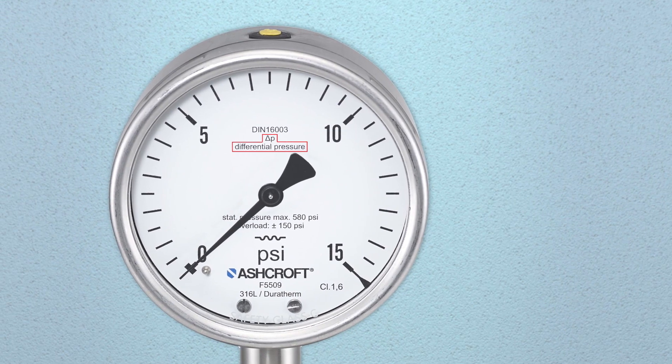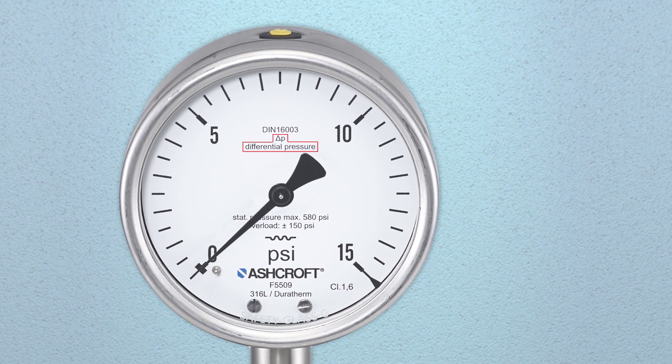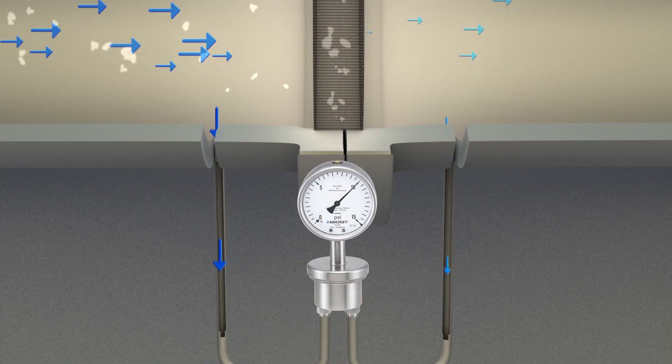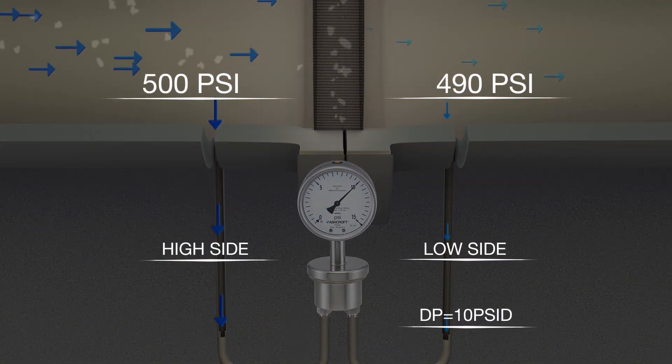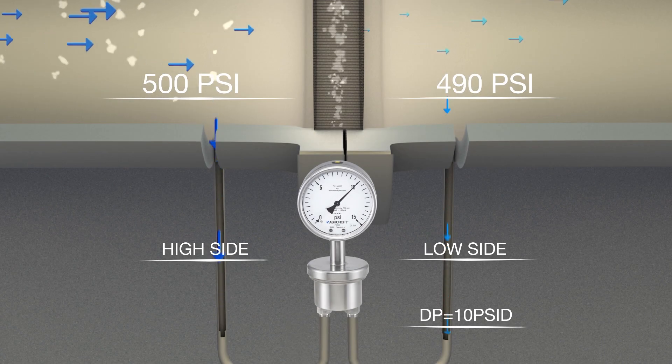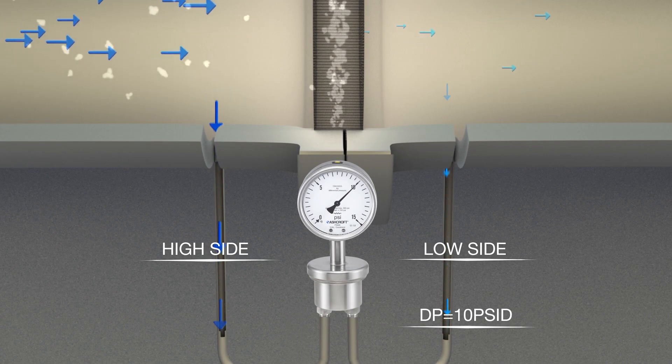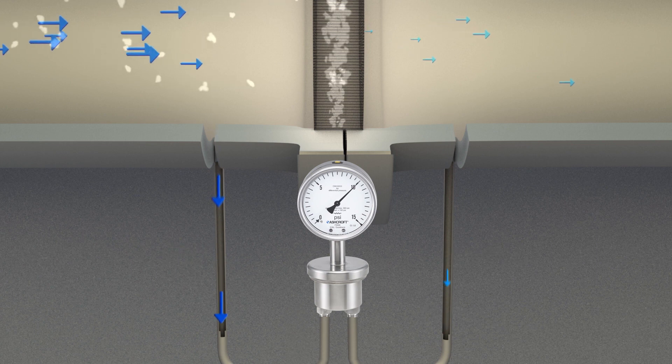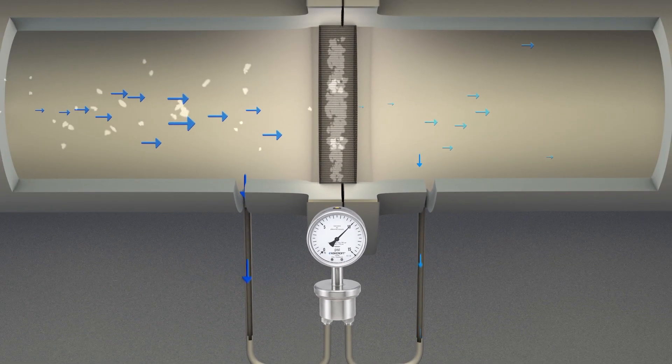The first is the DP range, which is based upon the most difference in pressure that the restriction is likely to produce. The second is the instrument's ability to contain the static pressure, which is simply the pressure in the line. While the differential pressure remains the same, a higher line pressure may require a gauge rated for higher static pressure.